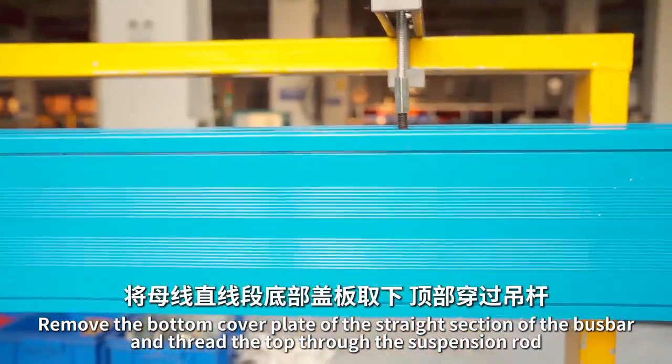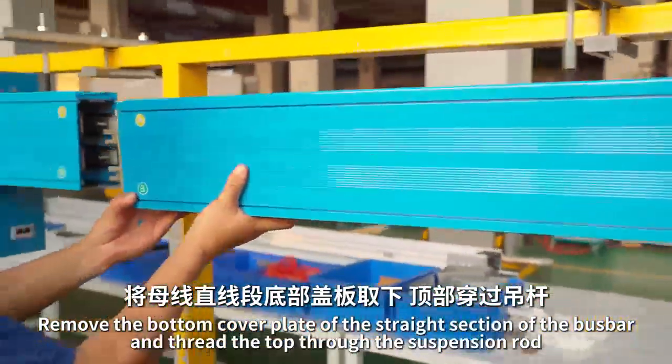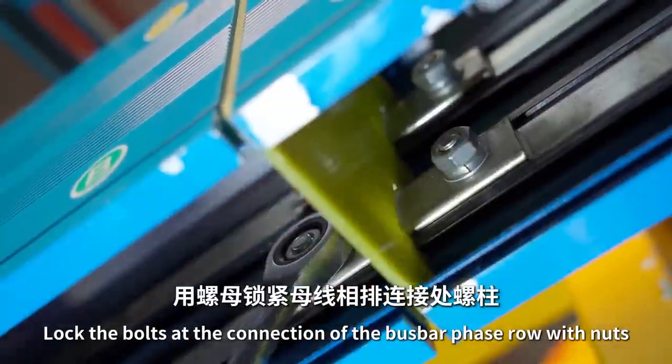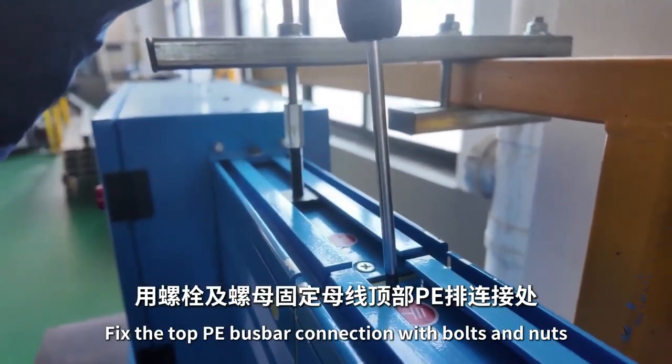Remove the bottom cover plate of the straight section of the bus bar and thread the top through the suspension rod. The protruding copper bar of the previous bus bar is embedded in another hole position. Lock the bolts at the connection of the bus bar phase row with nuts, and fix the top bus bar connection with bolts and nuts.